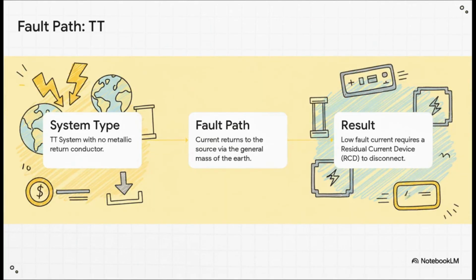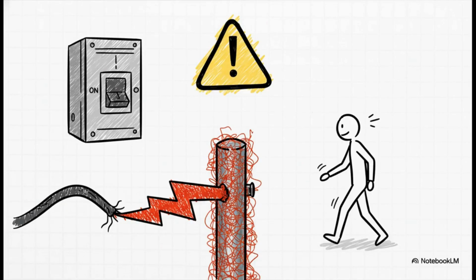And finally, we've got the TT system, which you'll often see out in more rural areas. Now, here's the big twist with this one. There's no dedicated return wire from the supplier. The fault current has to travel back to the source through the actual ground. And because soil has a pretty high resistance, the current that flows is usually too small to trip a normal circuit breaker. That is why these systems absolutely must have an RCD, or a residual current device. It's a super sensitive safety switch that can detect even a tiny leak of current and cut the power in milliseconds.